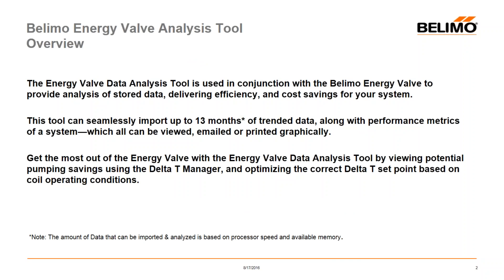The tool can seamlessly import up to 13 months of trended data stored inside the valve, along with performance metrics of the system, which can all be viewed, emailed, or printed graphically. You can get the most out of the Energy Valve Data Analysis Tool by viewing potential pumping savings using the delta-T manager and optimizing the correct delta-T set point based upon coil operating conditions.